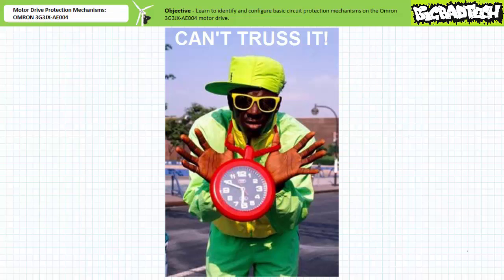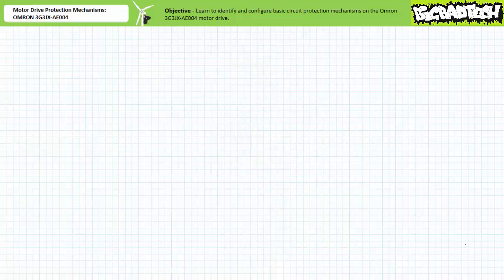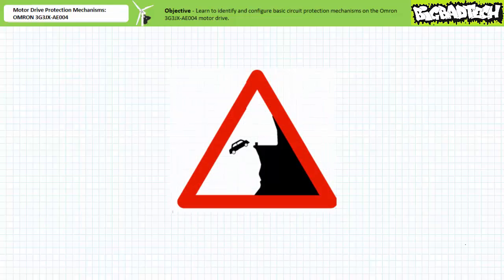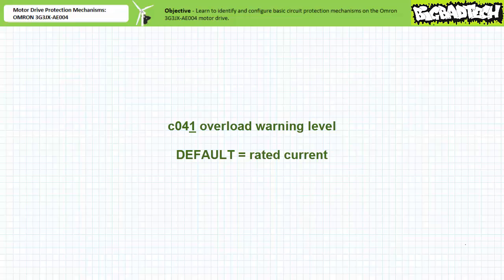Moving on, the OMRON 3G3JX AE004 motor drive, rather than just faulting out whenever an overload occurs, also allows early recognition and active limitation of overloads. Let's examine the early warning system first. An overload event might be thought of as a cliff you wish to avoid driving off. A warning in contrast might be a sign that says 'watch out, cliff ahead.' Communication parameter C041, overload warning level, serves as that sign before the cliff.